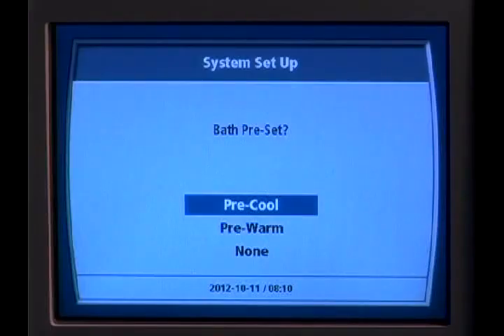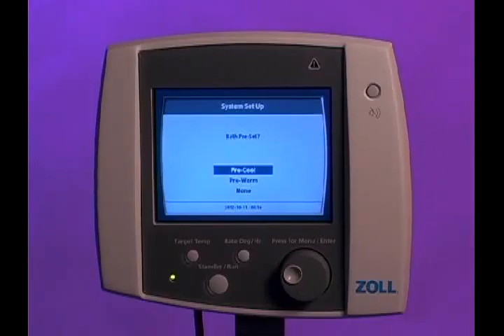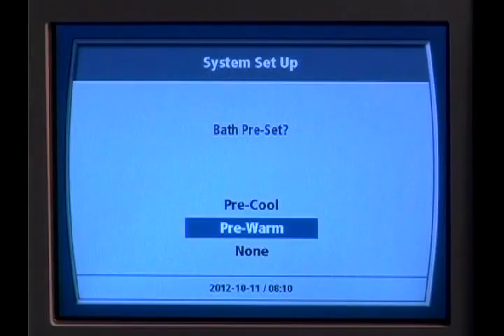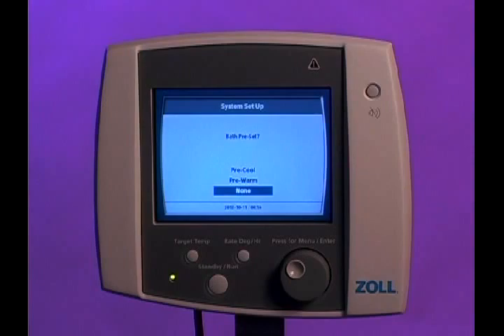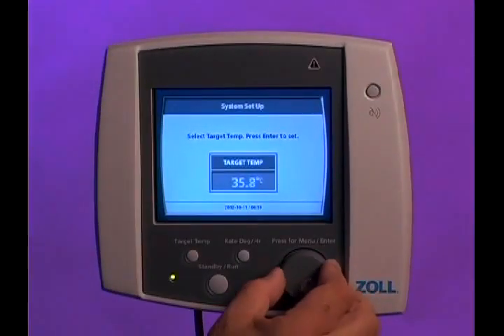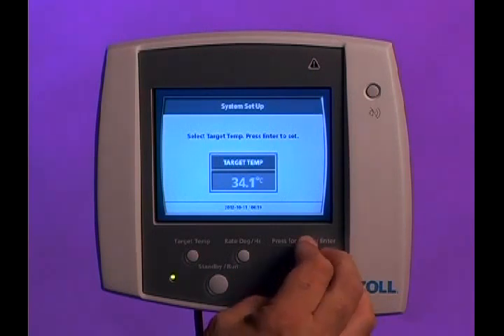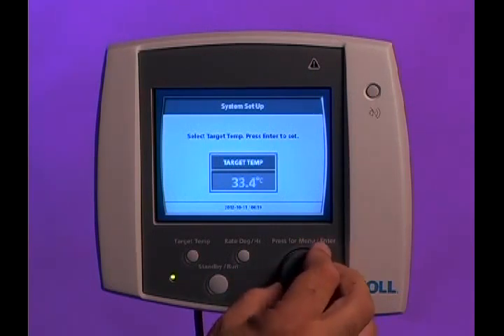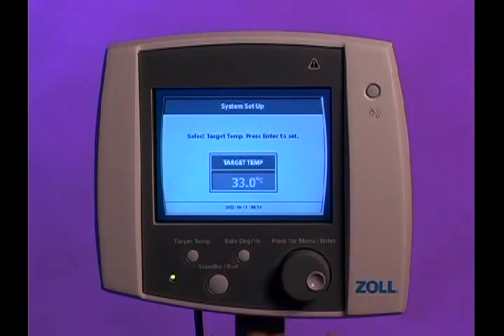To begin pre-cooling, select Pre-Cool by pressing the menu controller knob. If you plan to warm rather than cool the patient, rotate and press the knob to highlight and select Pre-Warm. But if you prefer that the saline remain at its current temperature, select None. Now the system asks you to select the target temp, which is the temperature you want the patient to reach. Rotate the menu controller until the desired temperature appears, and press the knob to select it.